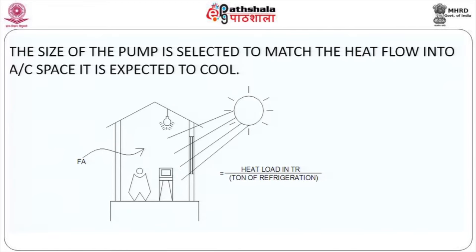The AC space is characterized as an enclosure — a room where you have internal loads and external loads coming in. The internal load could be any equipment, people, and lights. Likewise, the external heat loads could be solar radiation, the actual temperature difference between outside and inside, and of course the fresh air that you would normally take for such an application.